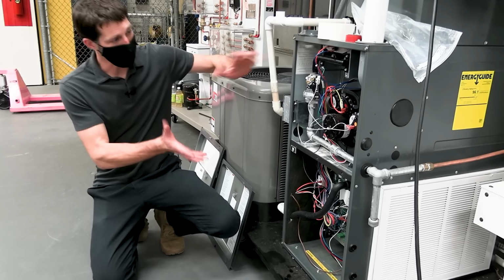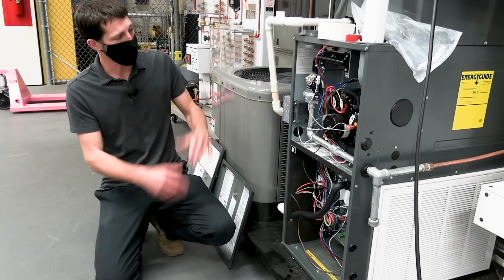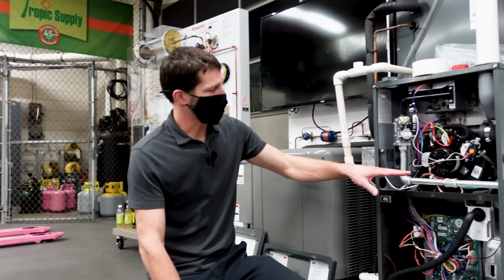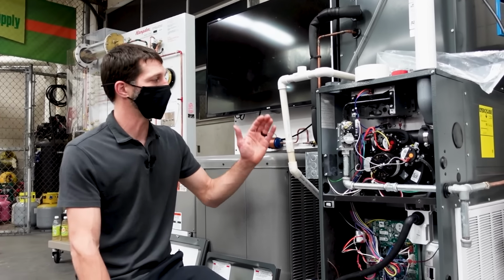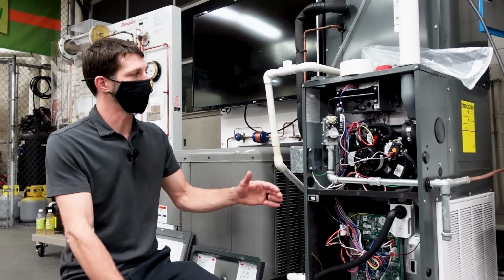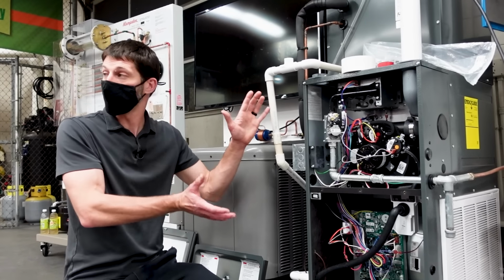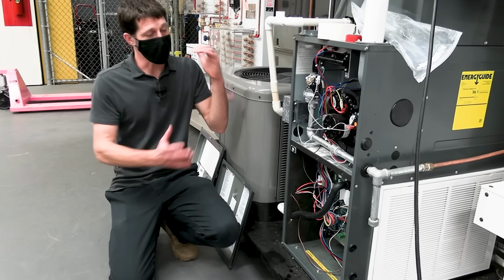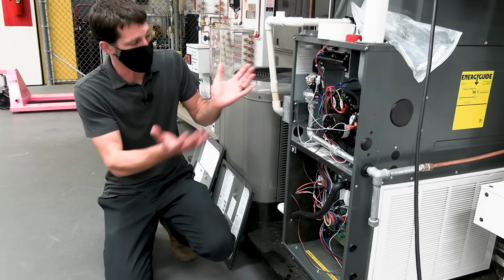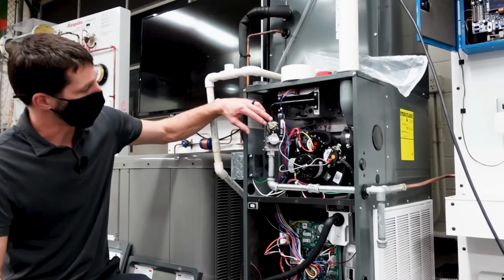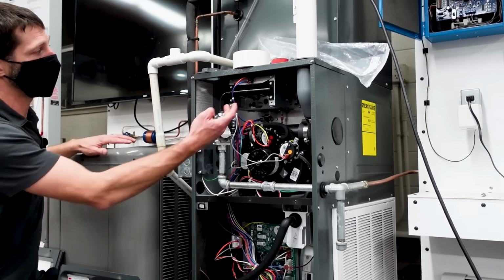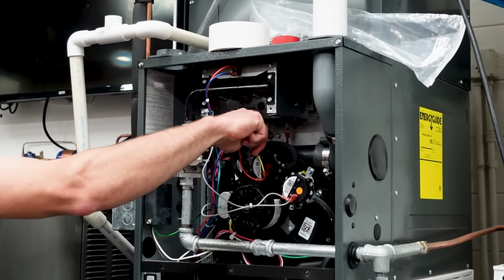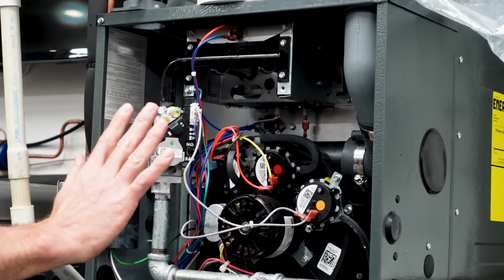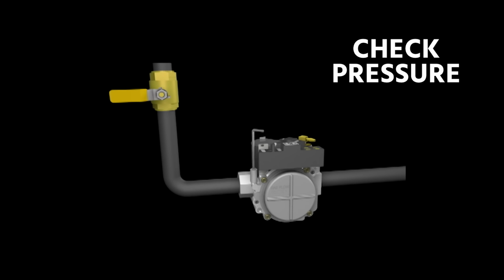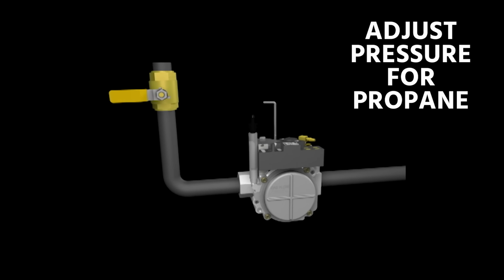So here you have a high efficiency gas furnace right here, and you can convert these from natural gas to propane and then back from propane to natural gas. So you buy these and they come as natural gas from the factory. If you were ever to change using the conversion kit from natural gas to propane, you're going to replace these springs right here. You're going to replace the two orifices here. There may be a plate here to adjust the combustion air, and then you're going to need to check your pressure coming in and going out, and you're going to need to adjust that for propane.